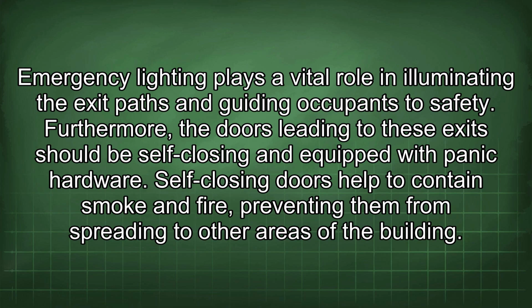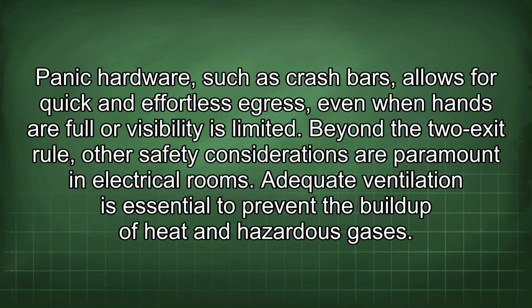Furthermore, the doors leading to these exits should be self-closing and equipped with panic hardware. Self-closing doors help to contain smoke and fire, preventing them from spreading to other areas of the building. Panic hardware, such as crash bars, allows for quick and effortless egress, even when hands are full or visibility is limited. Beyond the 2 exit rule, other safety considerations are paramount in electrical rooms.